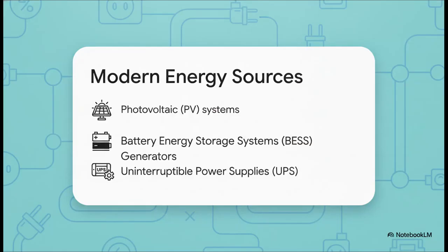And you know what makes this even crazier today is that modern job sites are way more complex and dangerous than they were in the past. It's not just a single feed from the street anymore. As the guidelines point out, we've got alternate supplies everywhere: solar panels, battery energy storage systems, backup generators, UPS systems. And all of these can backfeed energy right into your installation. Think about it. If you remove the multiple earthed neutral, the MEN connection, without all these alternate supplies fully isolated, you can create a literal lethal potential between the neutral and Earth conductors. You have to account for every single energy source.